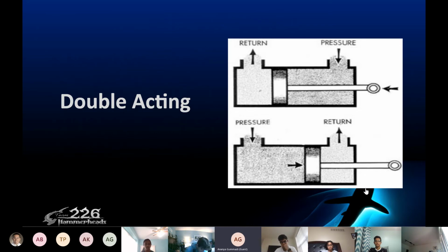Our code that programming writes is what moves that sliding valve from one side to the other to change which output port the air pressure is applied to, causing the cylinder shaft to move in or out. So when there's pressure in the system, pressure is always applied to one side or the other, and the key to that is that the double action cylinders stay in or out until you change the setting of the valve. Also, while the single action valves have one set of wires and connect to one port on the PCM, the double action valves have two sets of wires and take two ports on the PCM.